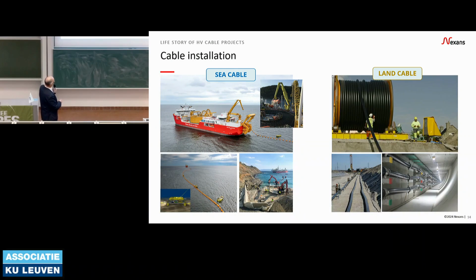You arrive then on shore, and you do the same thing with the land part. You have to unroll your cable to pull it into the trenches. Here it's a 4-circuit trench in 380 kV, partly underground. What you see here is what we call the snaking. It's just to compensate for the longitudinal elongation of the cable when it heats up due to the ampacity carried. And then once you have done both, you have to interconnect them.